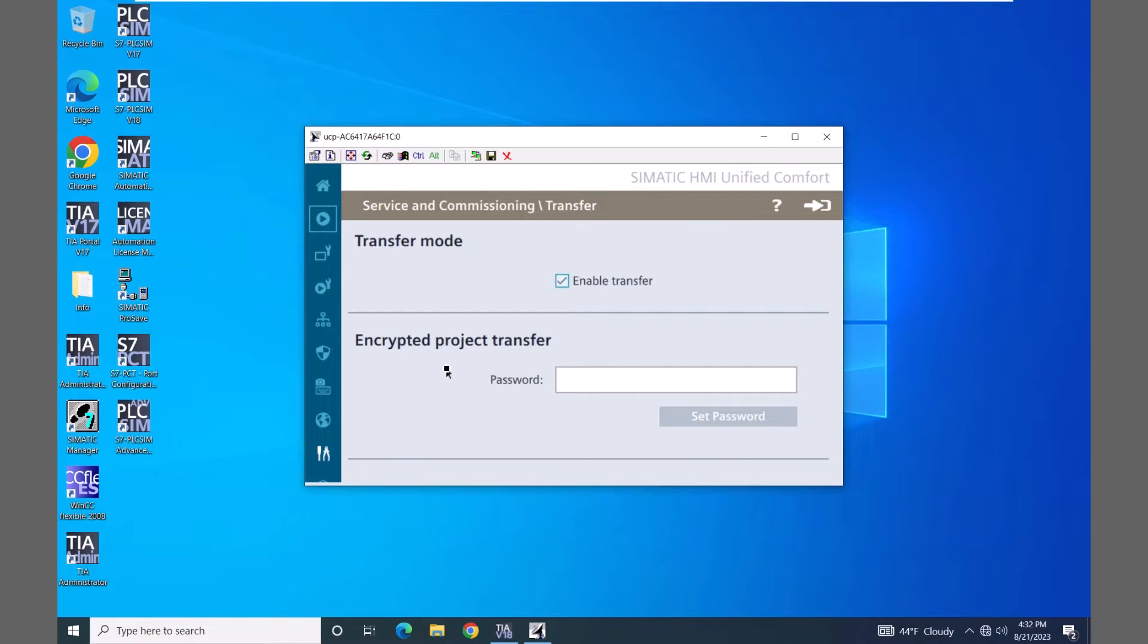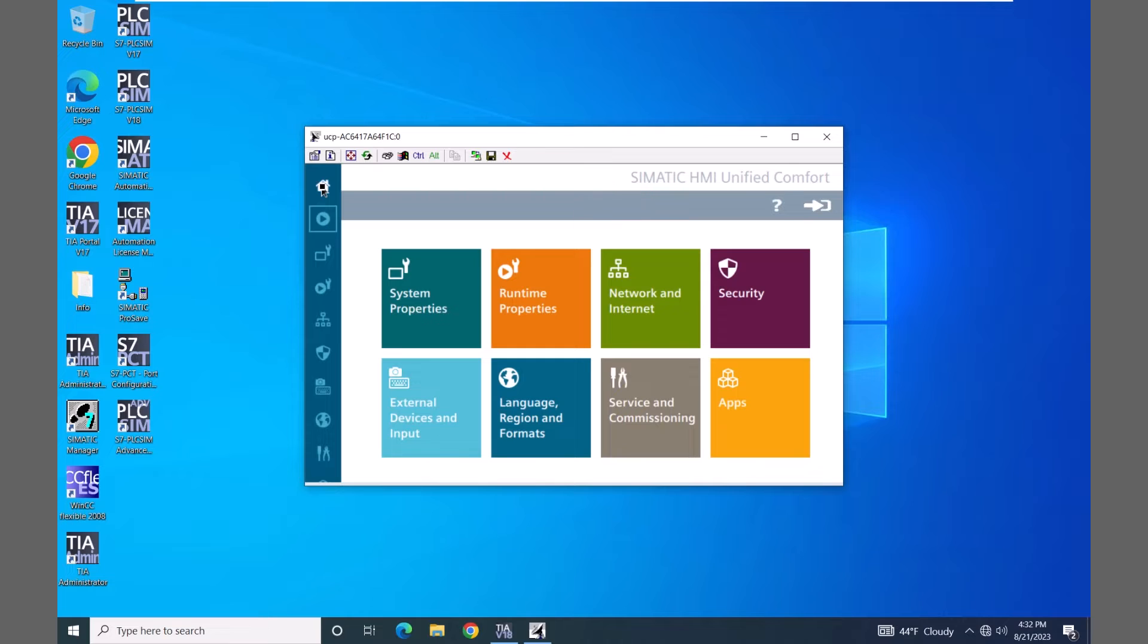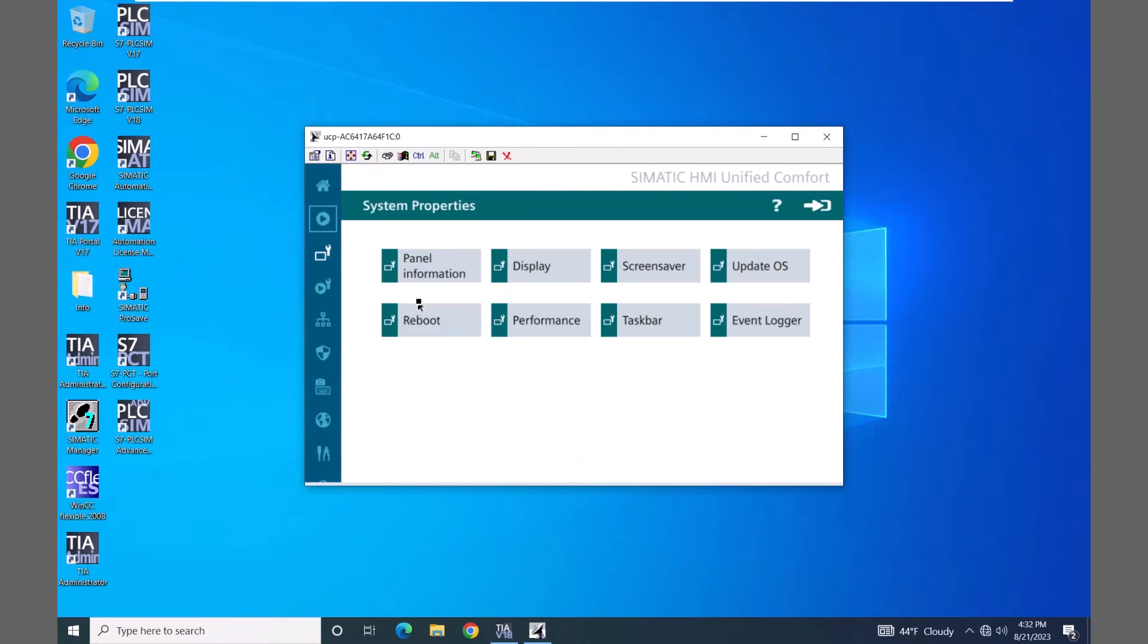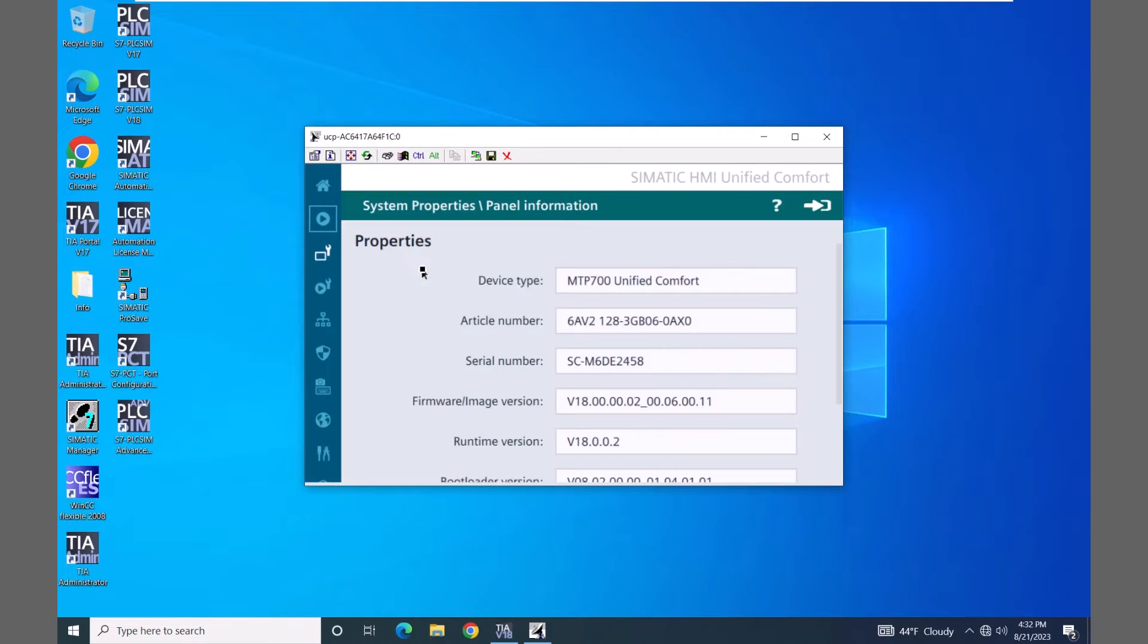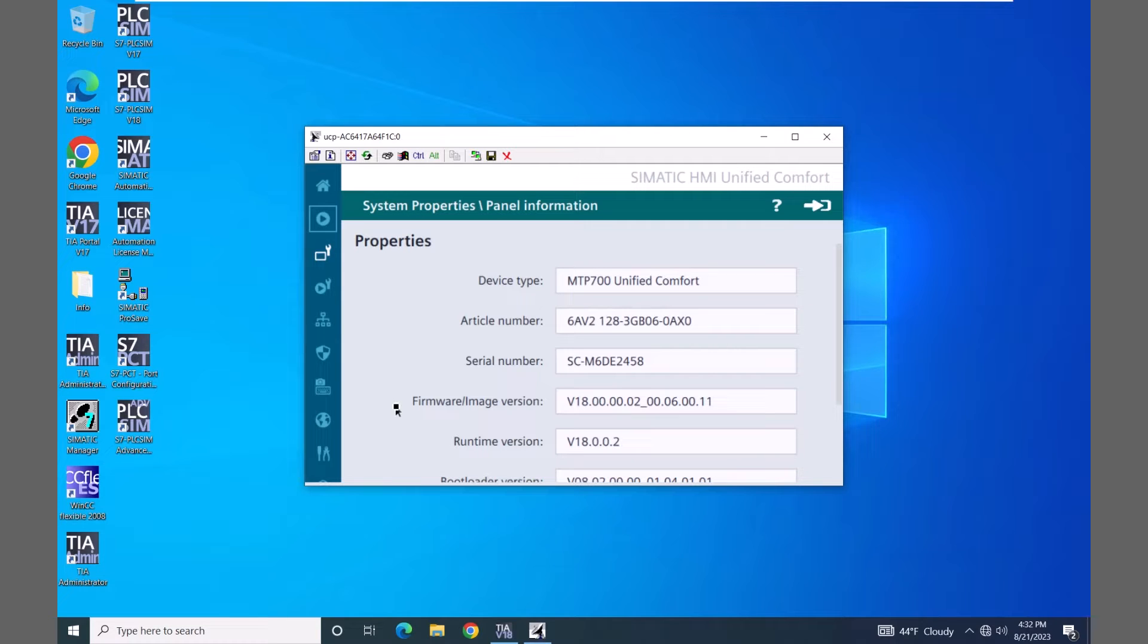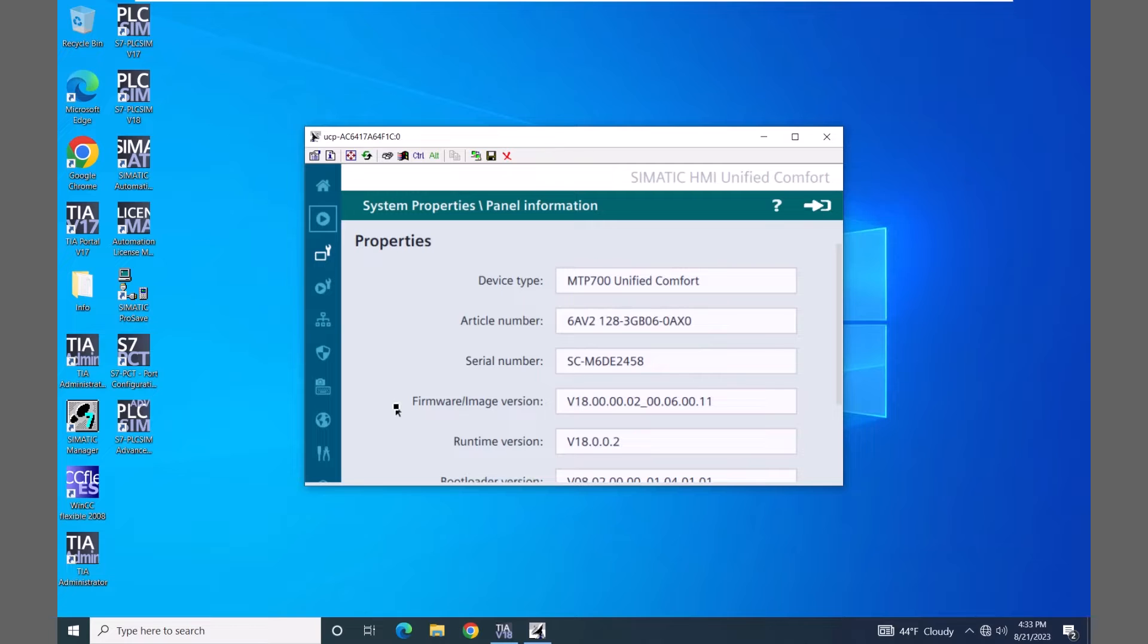I'm going to select home and go to the system properties and select panel information. There is a firmware/image version that is loaded on the unified comfort panel. You have to have an image version that is at least equal to the device version that you have configured in the unified comfort panel project.